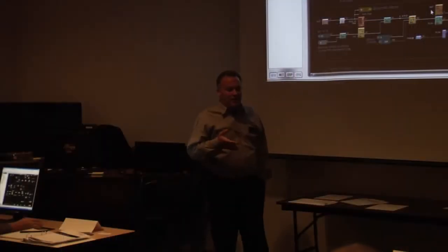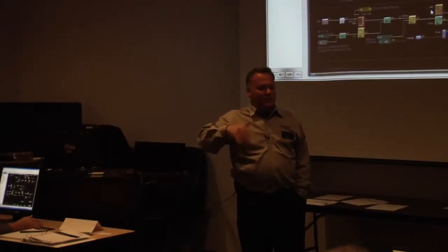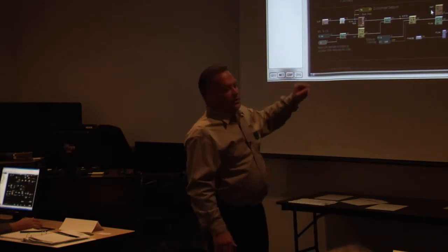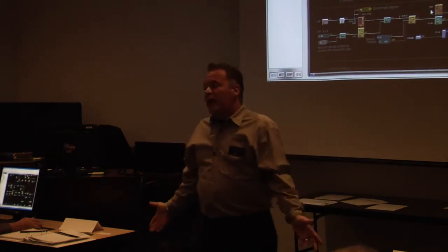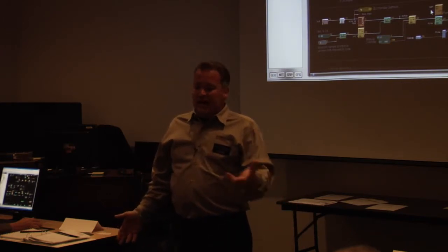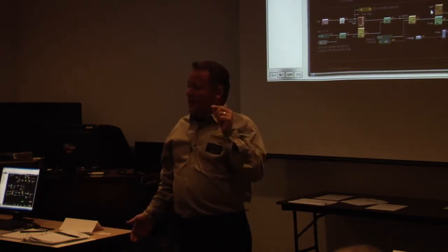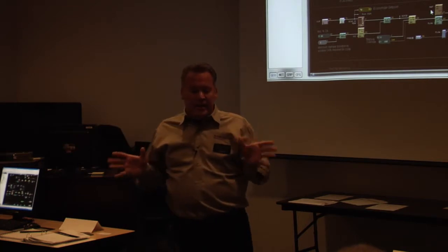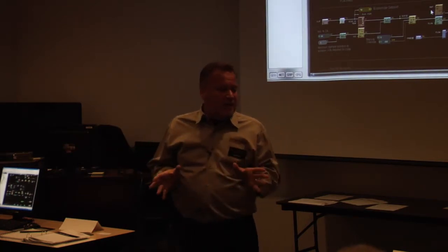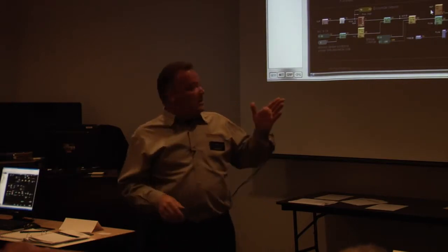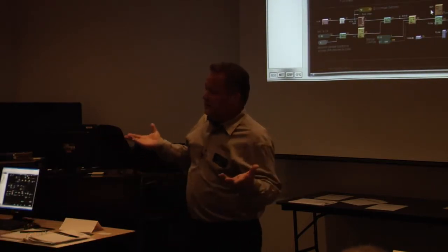When you have a 110 volt line and you want to add it to 2 places, what do you use? A wire nut. What they've done is they said, you know what? To prevent you from having to put those wires all over the screen, it'd be impossible to find if they're crossing each other, right? And the only 2 wires on the screen are dotted lines, which are digital. They're either transmitting on or off. So if I see a dotted line in my logic page, I only expect to see the words on or off, right? Like a dry contact, it's either on or off. If I see a solid wire, I expect to see any value, right? It's analog.